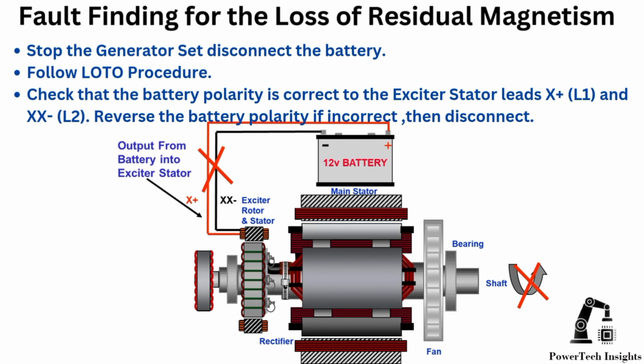Fault finding for the loss of residual magnetism. Stop the generator set and disconnect the battery. Follow lockout-tagout, LOTO procedure. Check that the battery polarity is correct to the exciter stator leads X plus and XX negative. Reverse the battery polarity if incorrect, then disconnect.